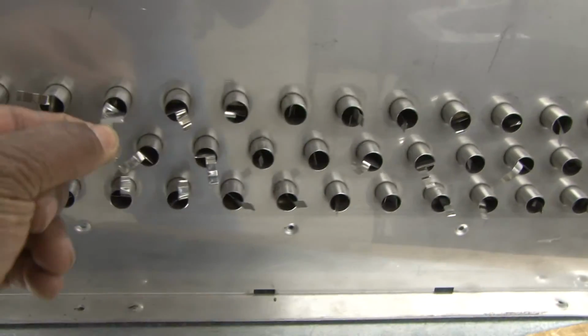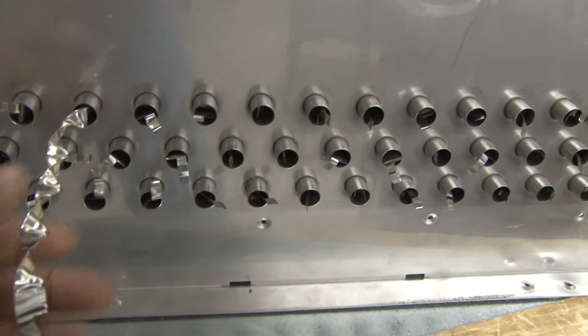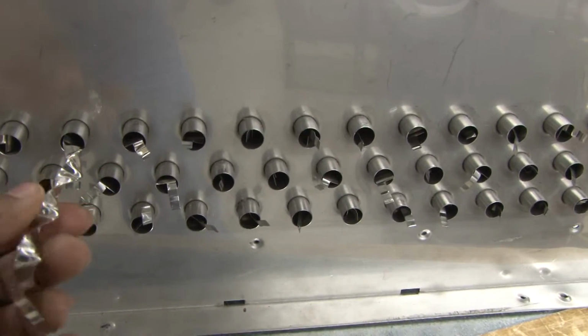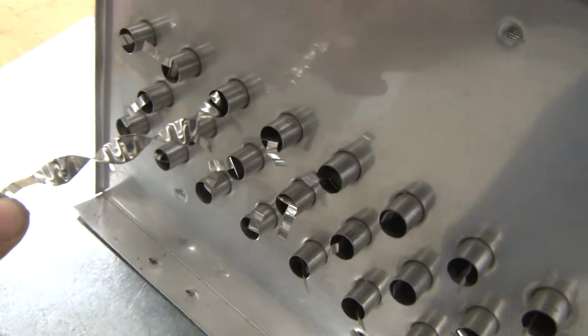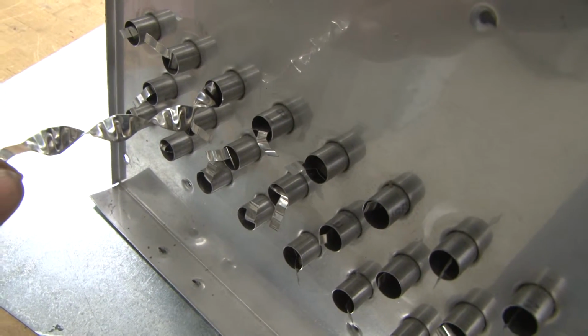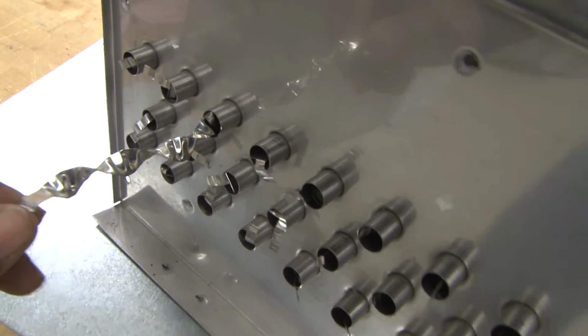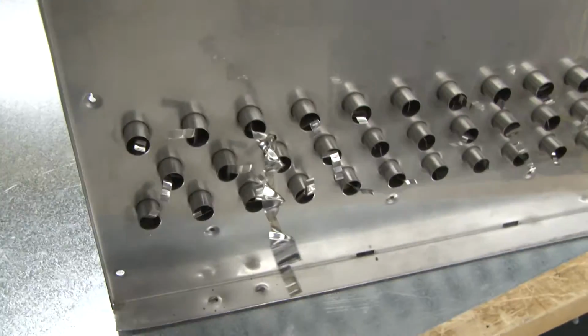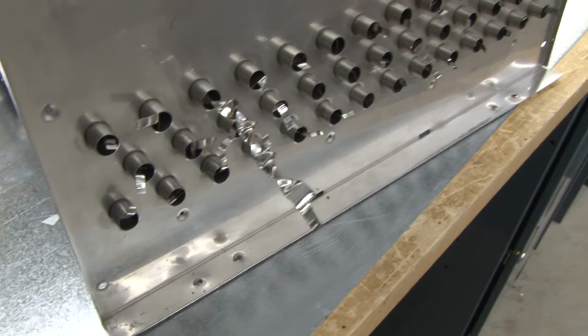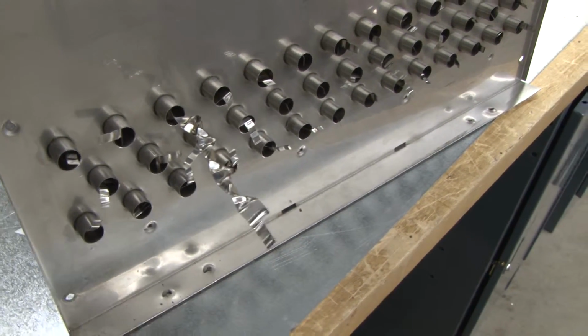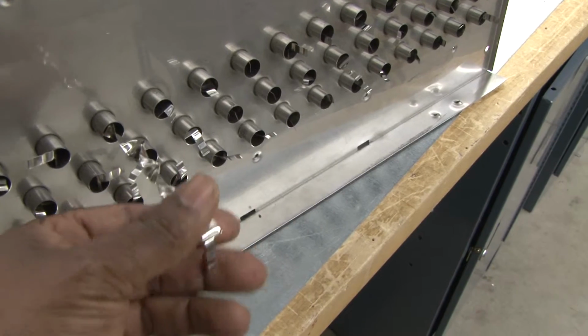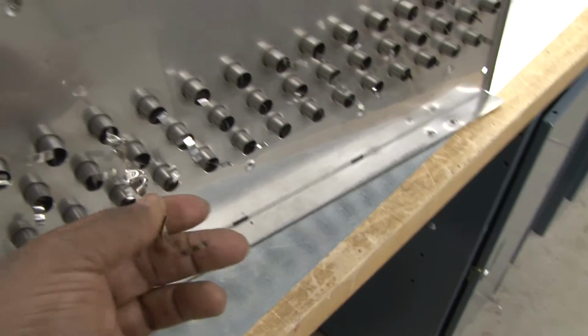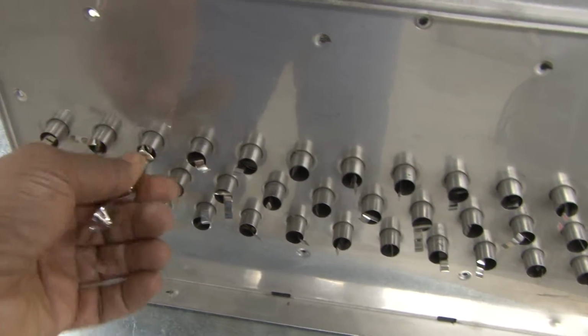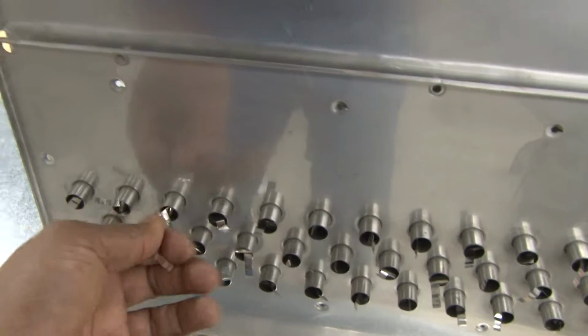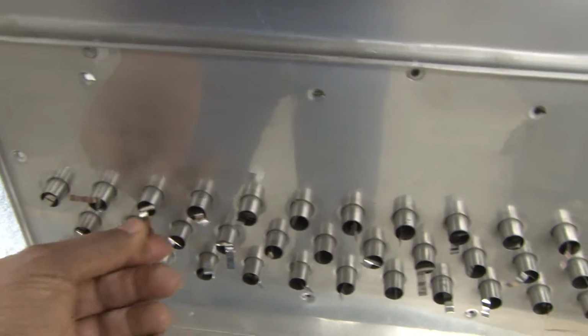Also inside of these, we have these little radiant panels inside of the secondary heat exchanger tubes. These panels are designed to slow down the flue gases to allow heat to be extracted from them while the gas slows down. These little radiant panels are made out of stainless steel so they don't rust, because the condensate is very corrosive, and if it was mild steel or aluminum, it would actually damage it and wear it out within a very short time.